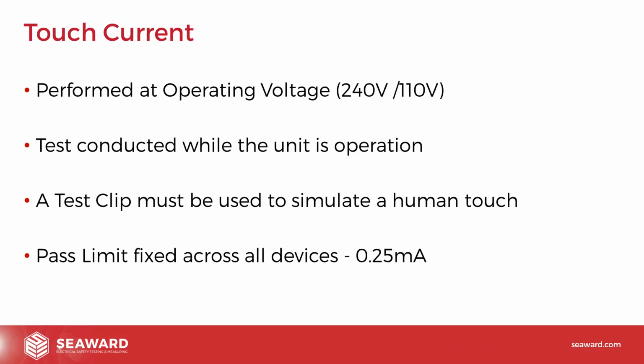Now very similarly, if we touch the class 2 product, there was no earth there for protection and the live cable was in contact with the outer casing, we would act as the return to ground, therefore we put ourselves in shock hazard. So that's why we perform the test, to ensure that there's no path that we could touch that would cause us any kind of injury. So as we said, during the test, the current flows back into the device via the test clip.